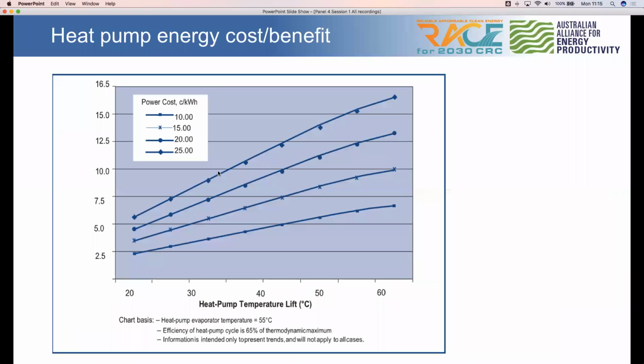Looking quickly at the cost benefit for heat pumps, this is an analysis that was carried out in Australia. On the left axis, you've got dollars per gigajoule. Then through the lines, you've got cents per kilowatt hour for electricity. On the bottom, they're looking at the degrees of heat lift. You'll see just how incredibly cheap the heating costs can be using a heat pump, especially when you've only got, say, 20 or 30 or 40 degrees of heat lift and very cheap electricity. It certainly comes through as a very low cost heating option.